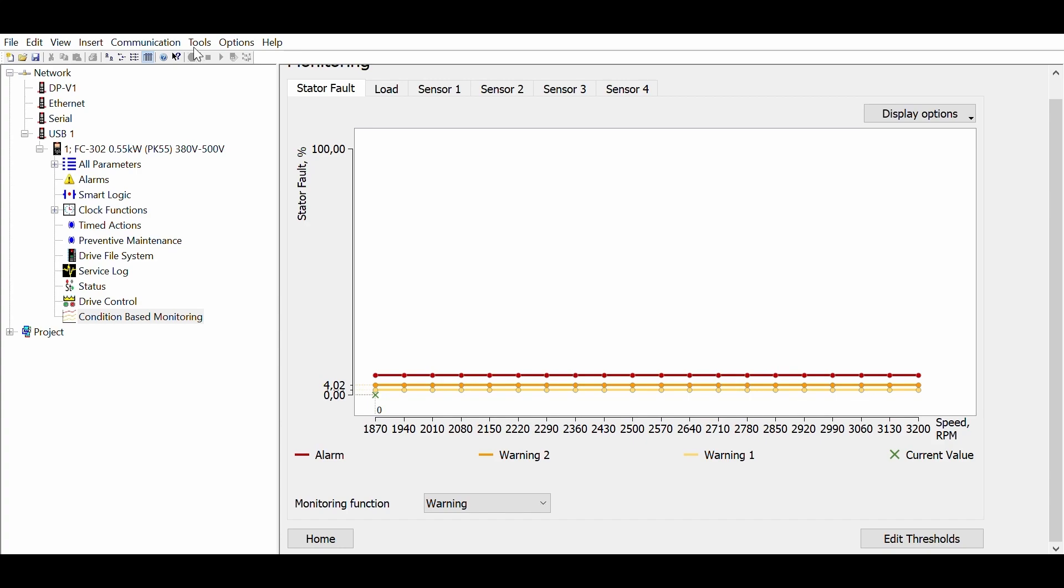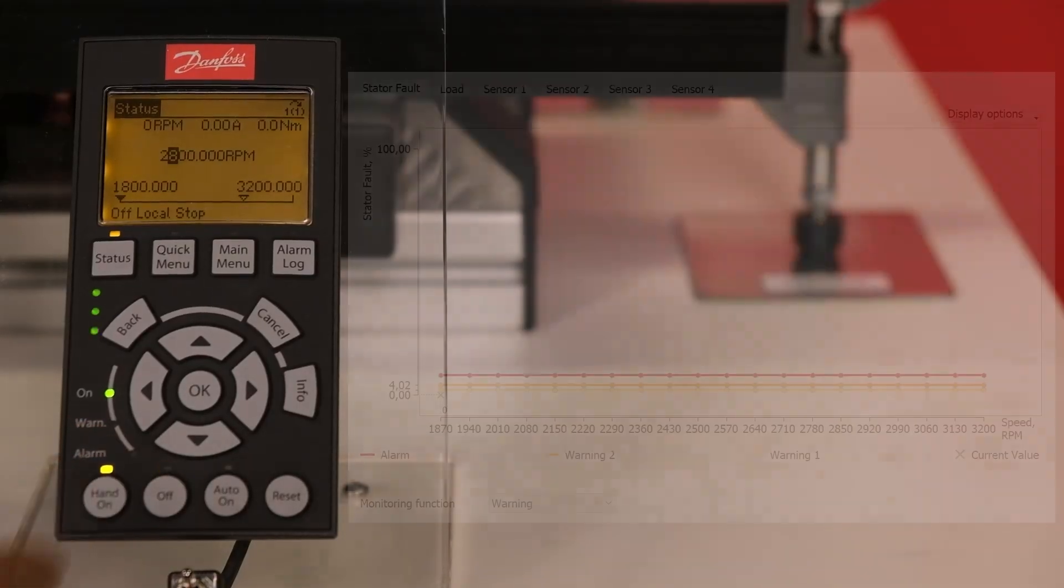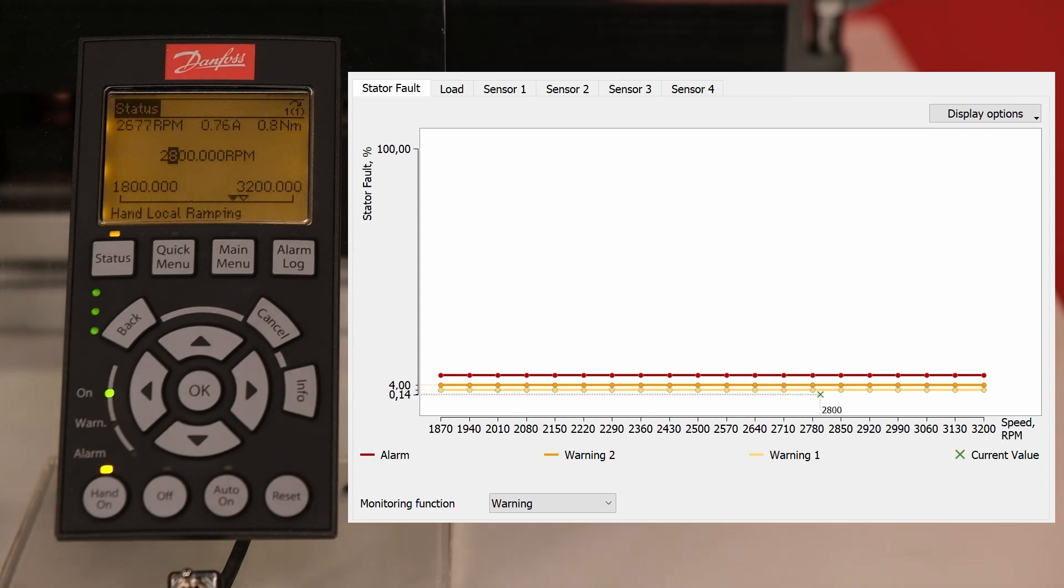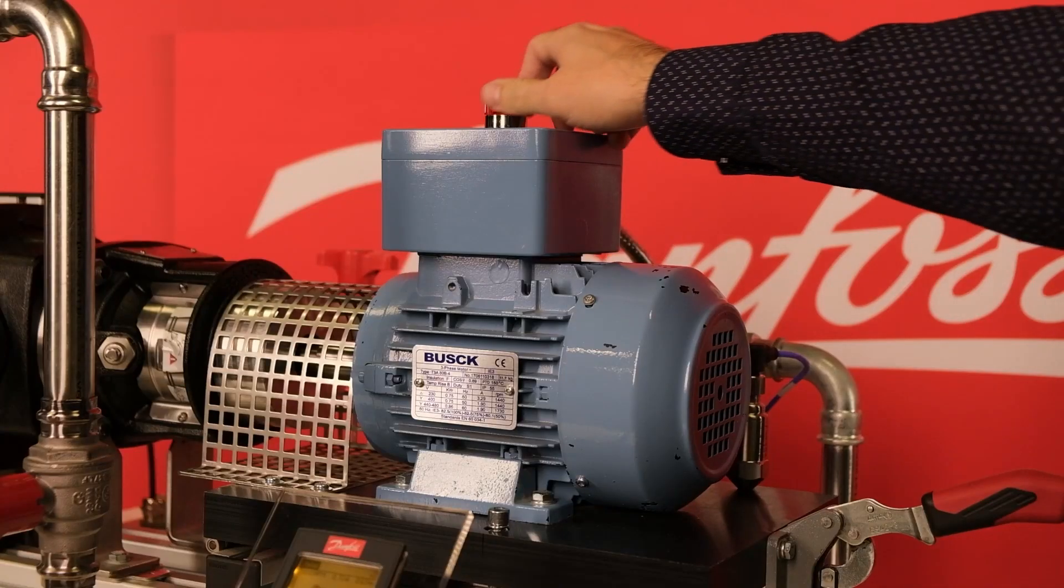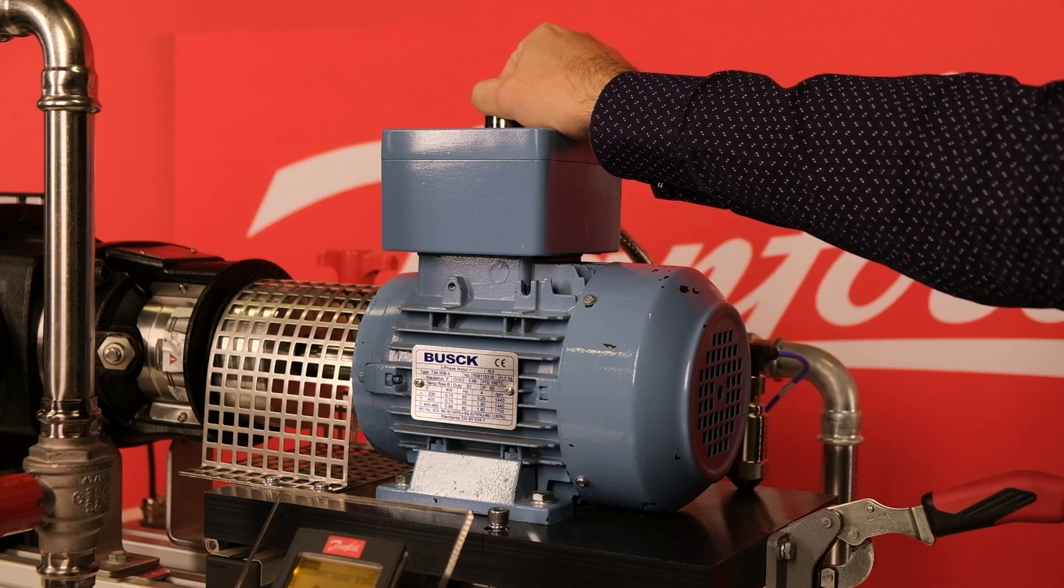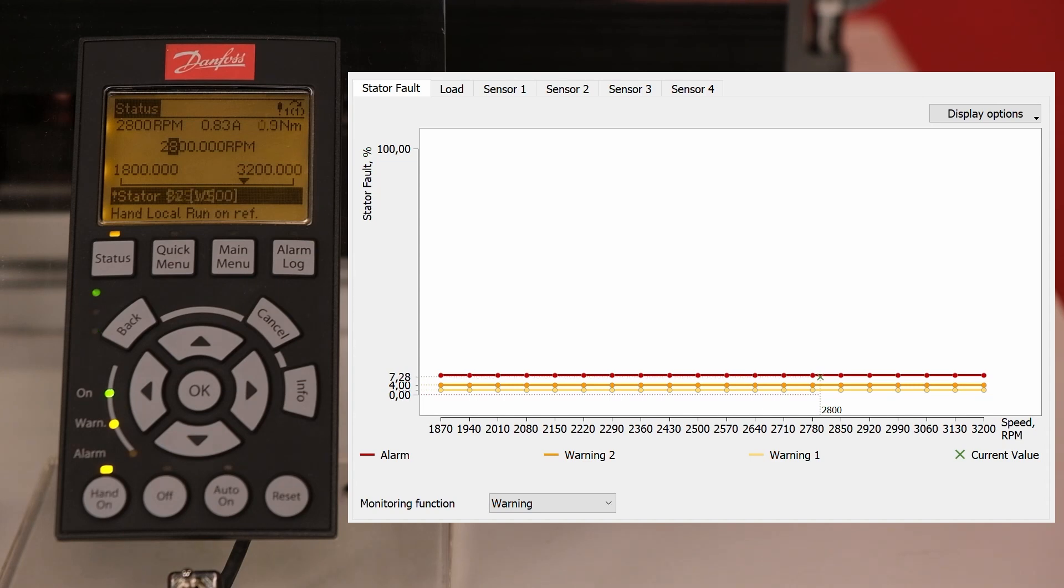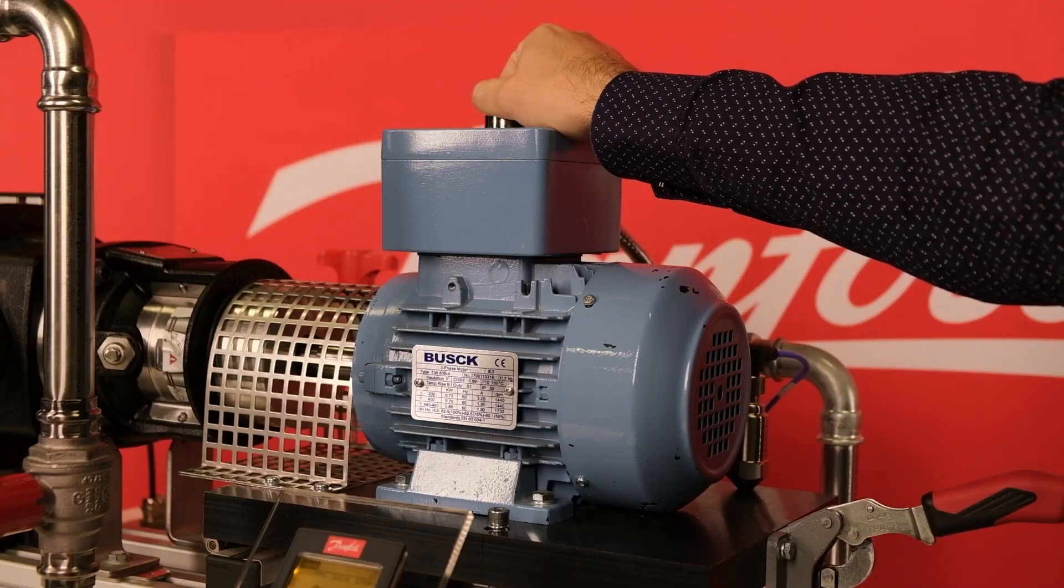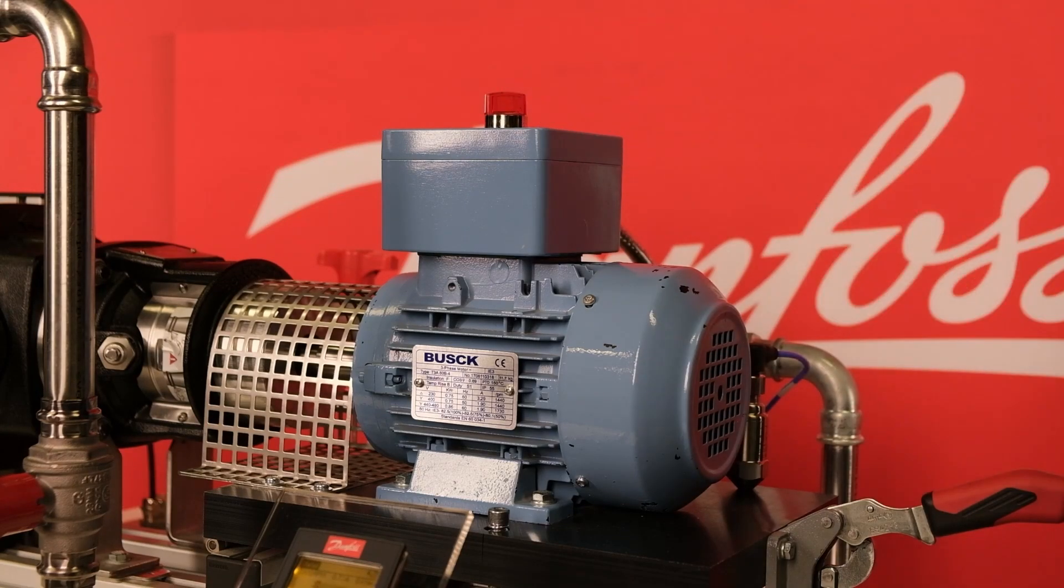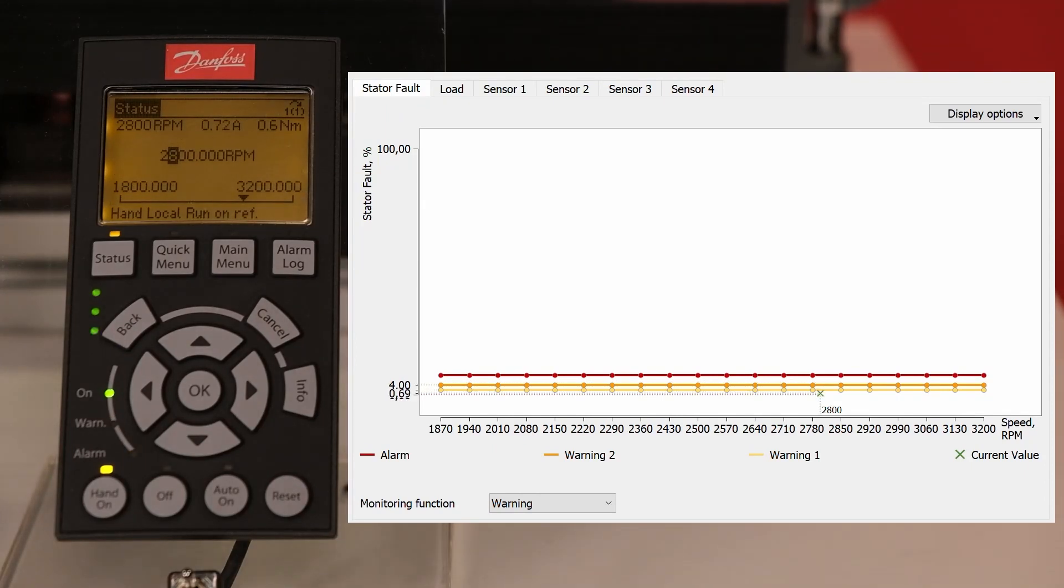We will now start the drive and simulate some faults to see how CBM works. A small green cross indicates the actual value of the monitored parameter. Let's start with a turn-to-turn winding fault, simulating an incipient winding isolation fault. The motor keeps running but the drive detects an increase of the stator winding fault signature and will display a warning message. Once the fault is removed the warning will disappear.